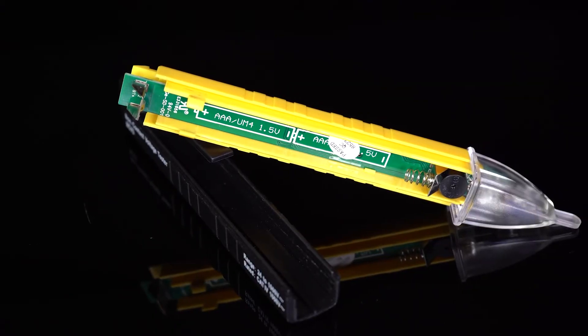One good thing that we always recommend anytime you're using something non-contact voltage, before you just go out and say it's live, go to a circuit that you know is live just to make sure your batteries are good and check it. Say okay, yep, my instrument's got good batteries, so let me go over now and check the circuit. I've made sure that I've flipped the proper breaker.